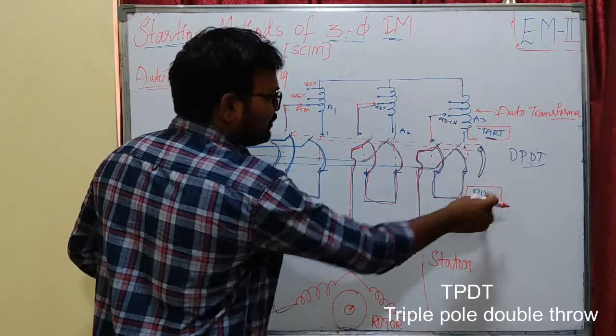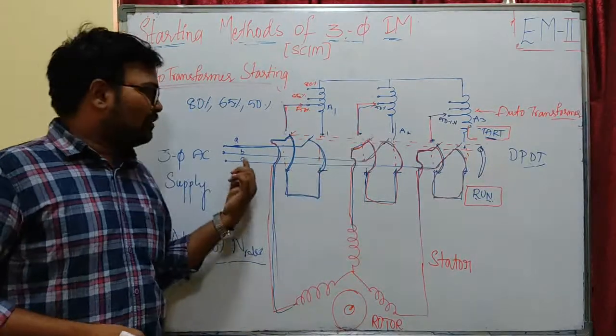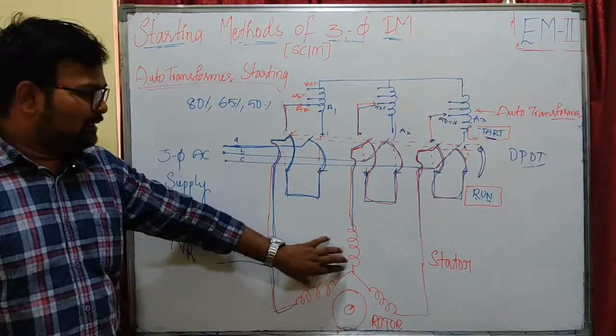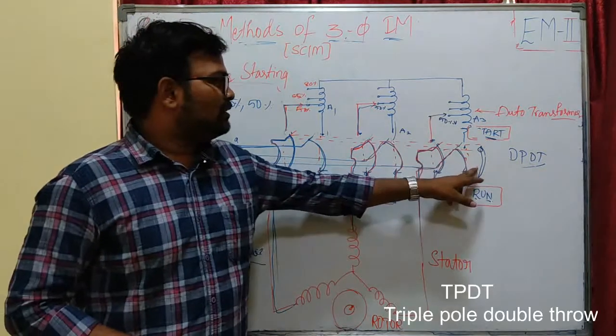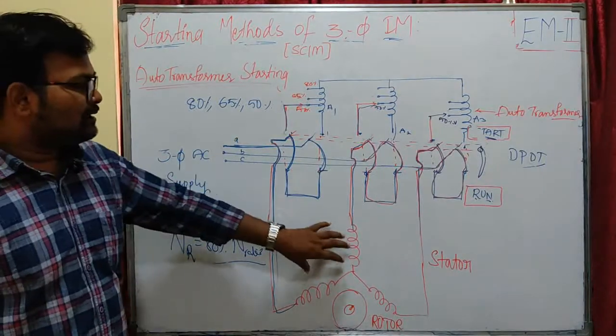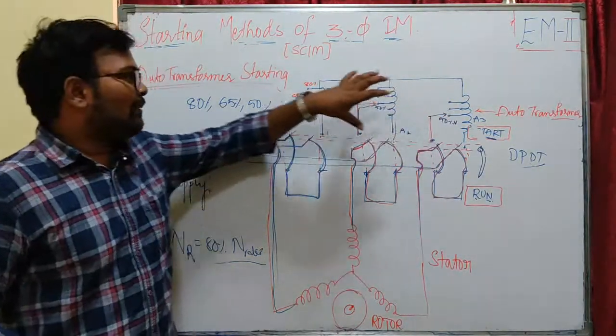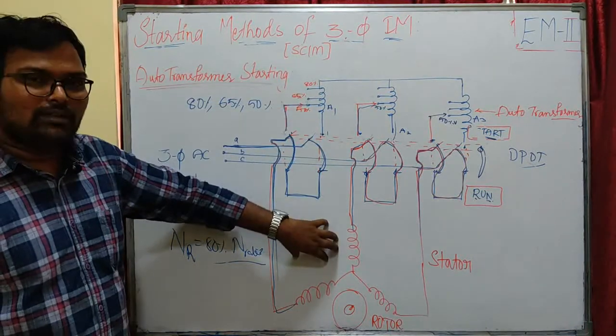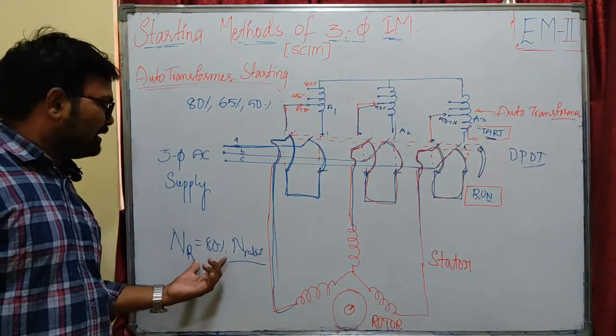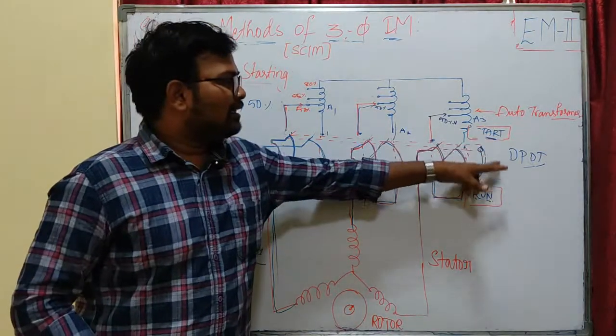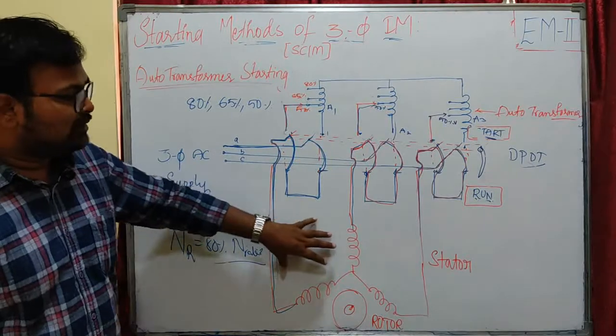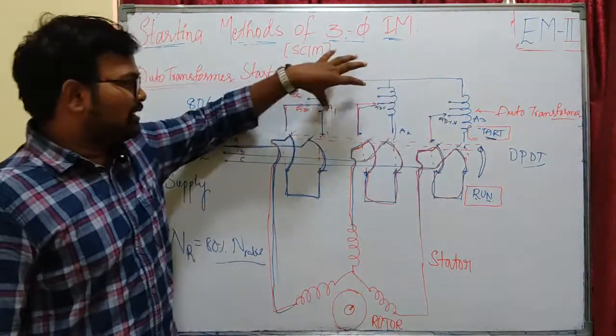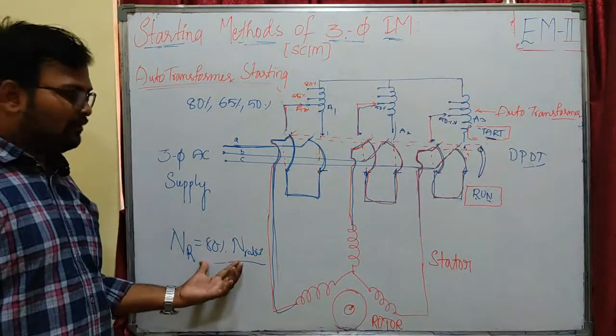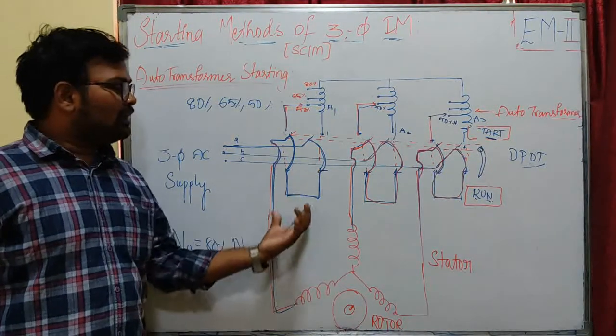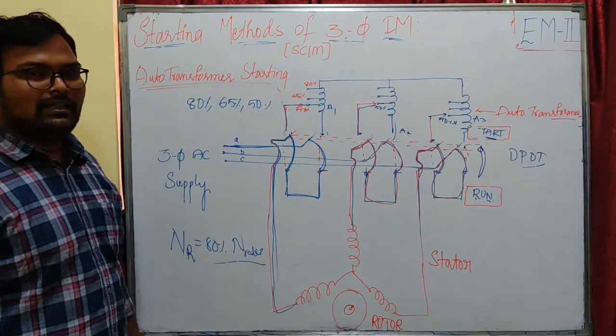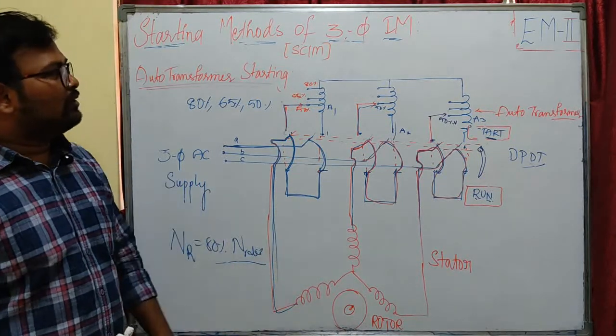When I switch my DPST to the run position, our auto transformers are disconnected from the supply, and the supply voltage is directly connected to my stator winding. That means whenever this DPST switch is in the starting position, our AC supply is supplying the stator through auto transformers with some tappings. That means reduced voltage is applied to the stator at the time of starting. Whenever our rotor attains 80% of rated speed, let us say, our switch will be turned to the run position. That means our AC supply is directly connected to the stator winding, and we are bypassing the auto transformers. That means we are disconnecting the auto transformers whenever our machine attains 80% of rated speed. So under running condition, we can apply the full voltage to the stator winding so that our machine will run at rated speed. So this is how we are going to deal with auto transformer starting.